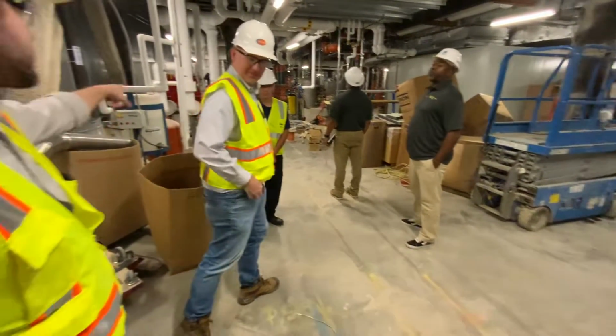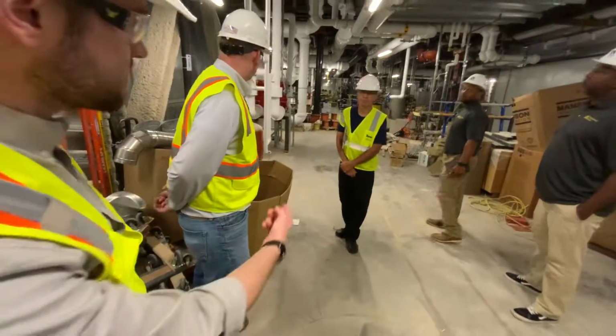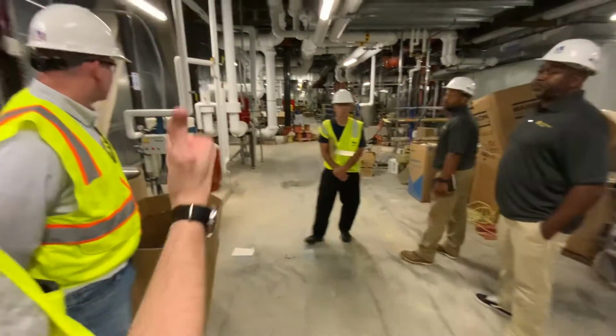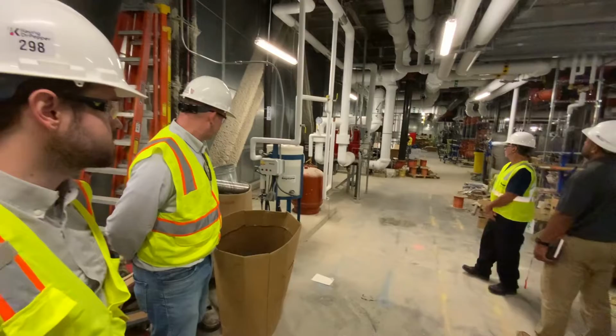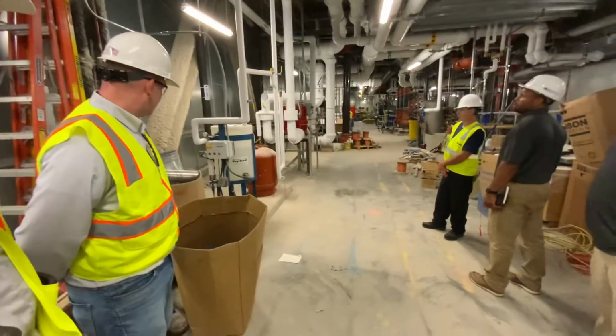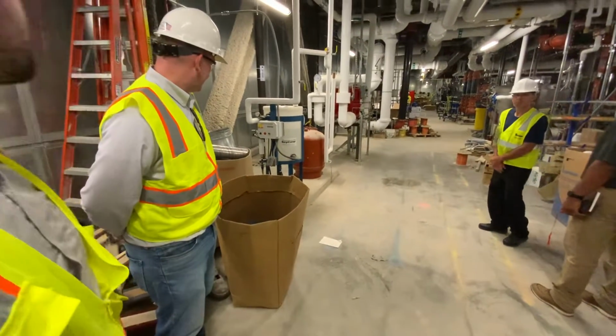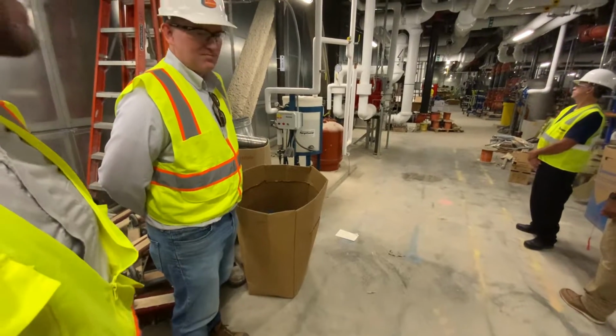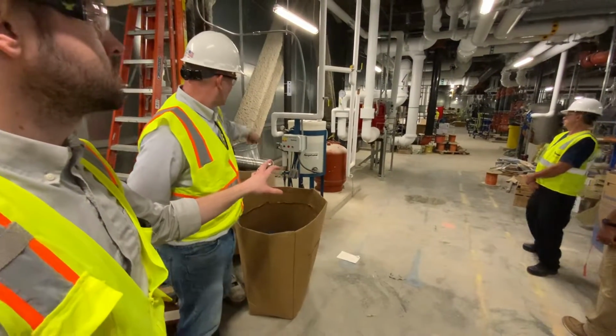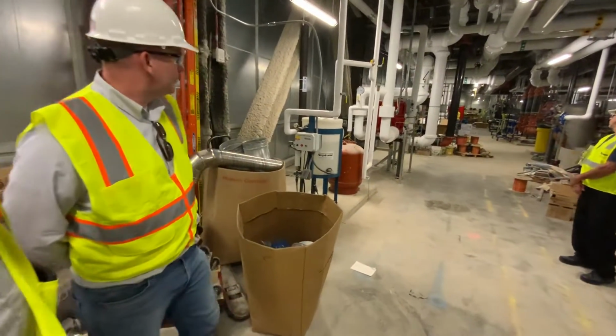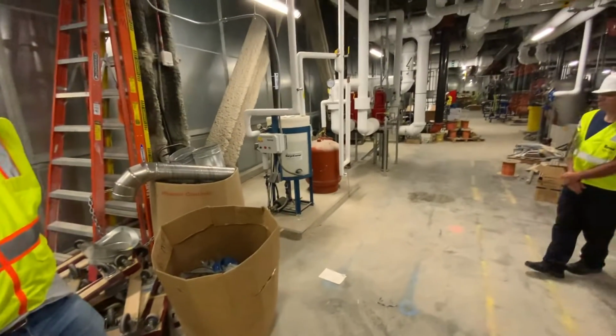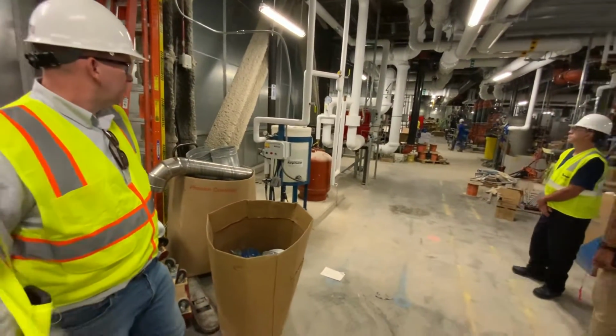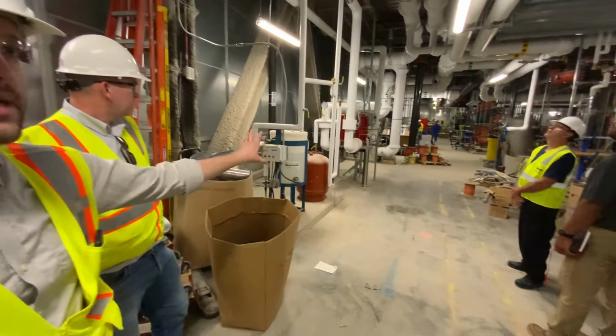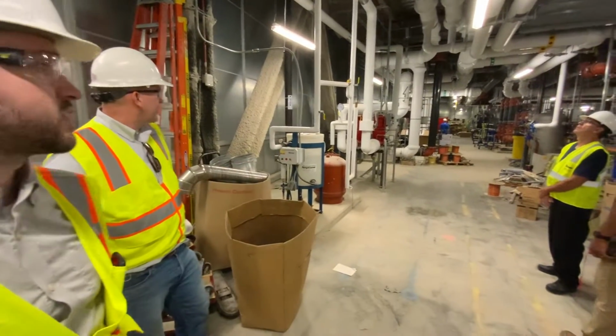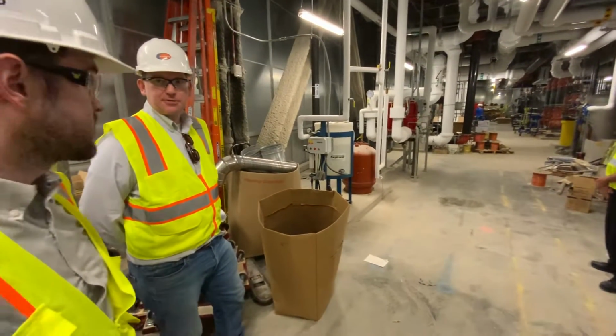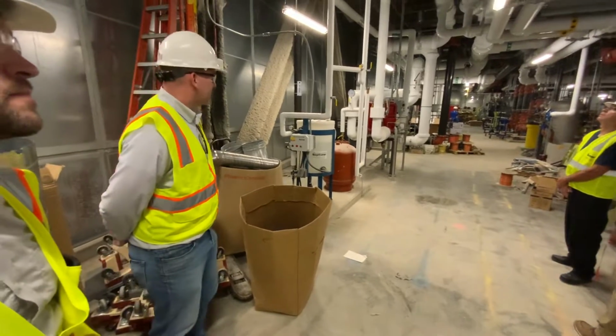As mentioned, this to our left is the pump skid for the energy recovery, for the glycol system. Where did they mount the controller for that? I actually think we're controlling that off of the Air Handler 6 controller as well—it's just pump start, stop, and some temperature sensors that come over. It doesn't even have VFDs, just starters, so it's a very simple setup.